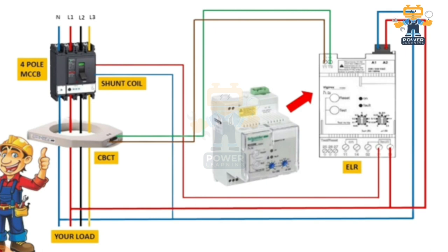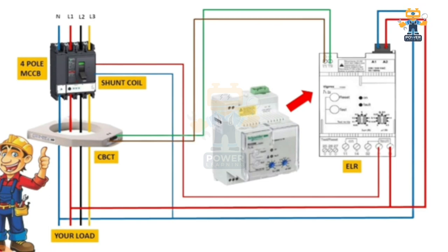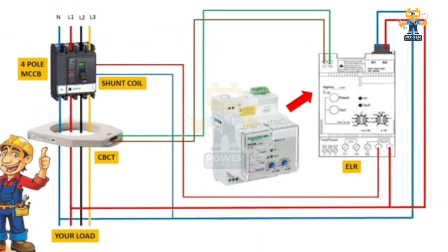To summarize: this is a simple wiring setup. The four-pole breaker has incoming supply and outgoing supply towards the load. On the load side we connect the CBCT, which has two wires connected to T1 and T2 of the earth leakage relay. A1 and A2 are the earth leakage relay power supply. The relay contact shown here operates the shunt coil to trip the breaker when leakage is detected.